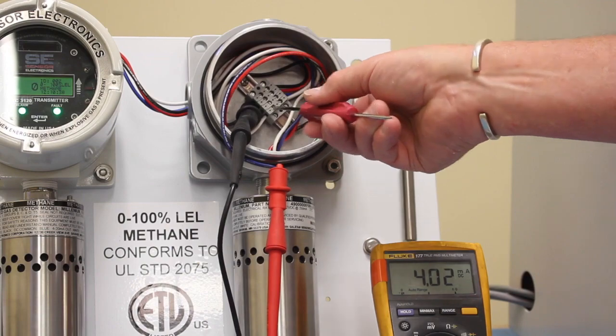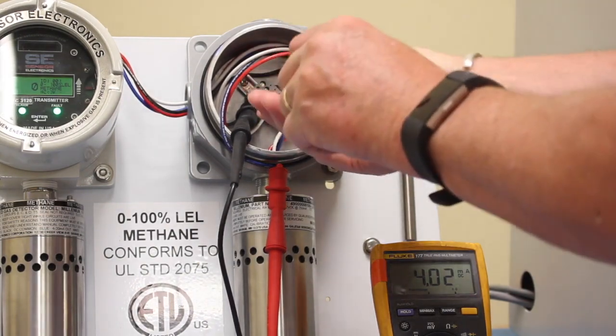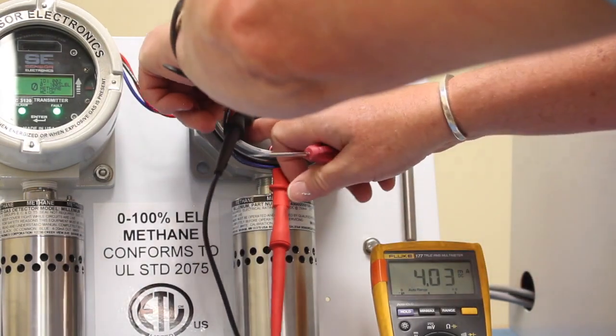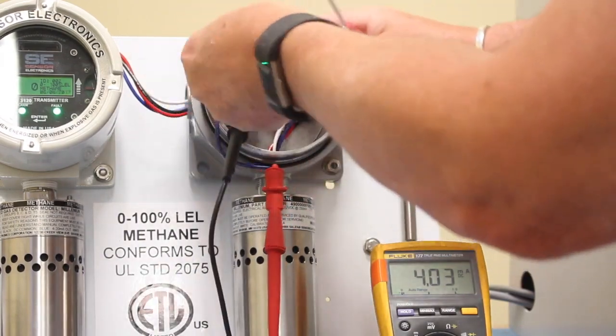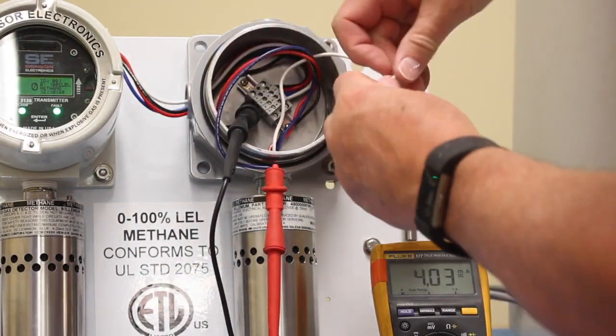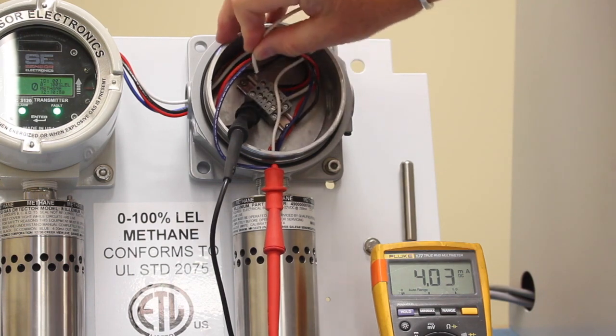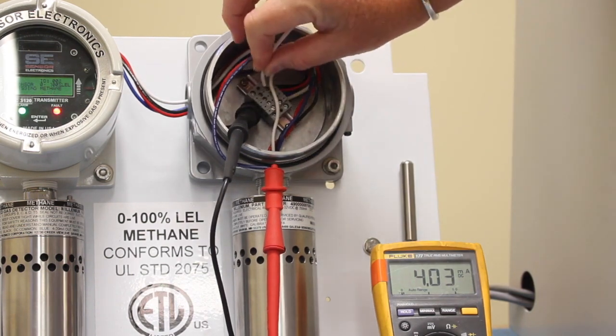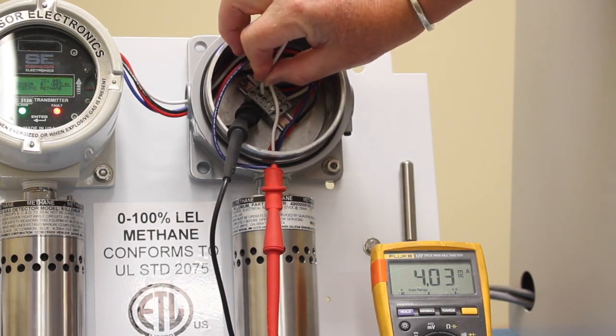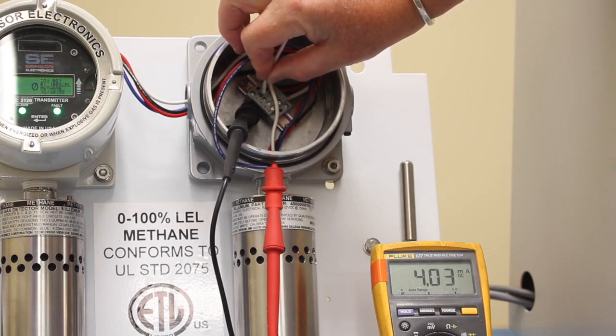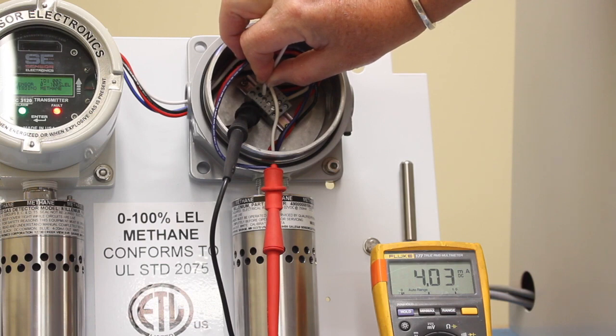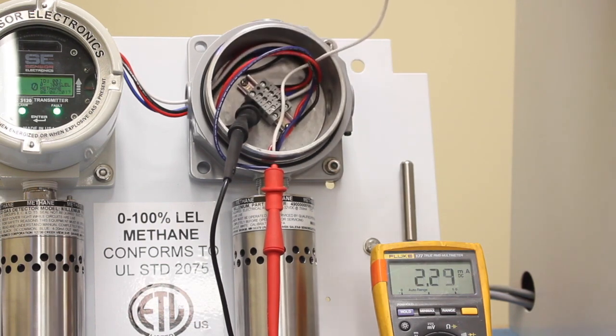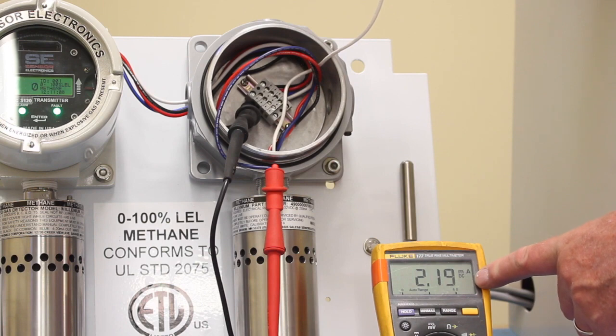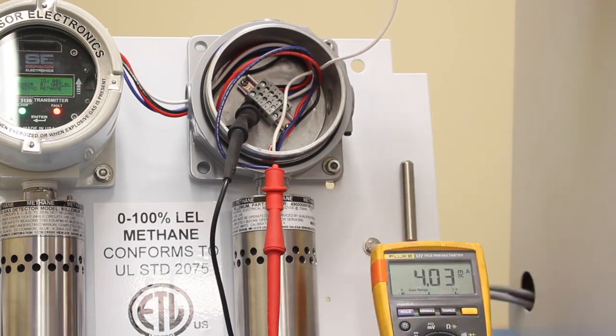So if it is connected to a terminal, you take the white wire off and connect it to DC common, which is the black wire of the sensor, for 10 seconds. Once you break it, you'll see it drop down to 2.2 milliamps. That's a zeroing mode, and it just goes back into normal operation then.